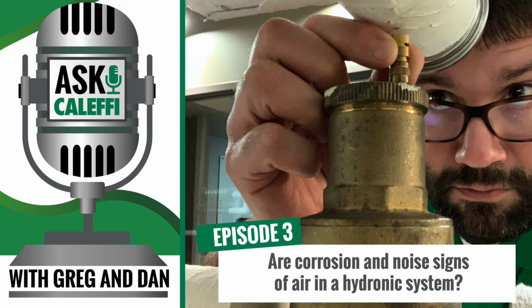You might have three 200,000 BTU boilers, so you're looking at 600,000 BTUs. On an individual application, you're probably at a 20 degree delta T, so you're going to be 20 GPM per boiler. But when you're sizing that separator, if you're putting it in the header pipe, you're going to need to figure for that total load, or 60 gallons per minute.